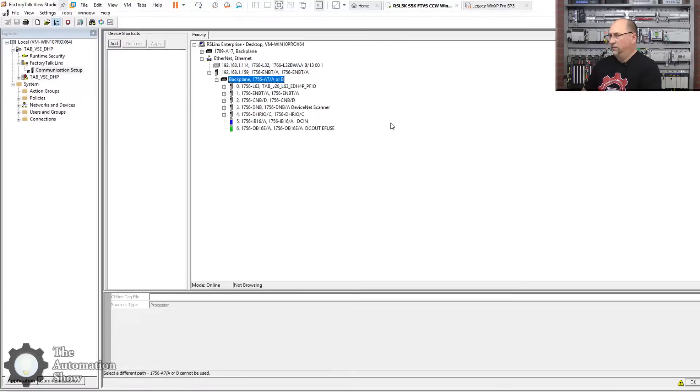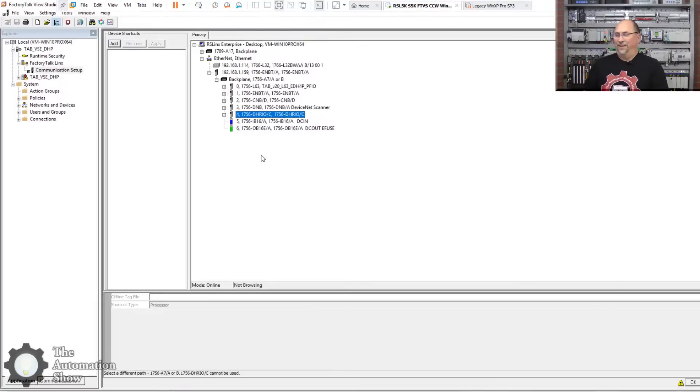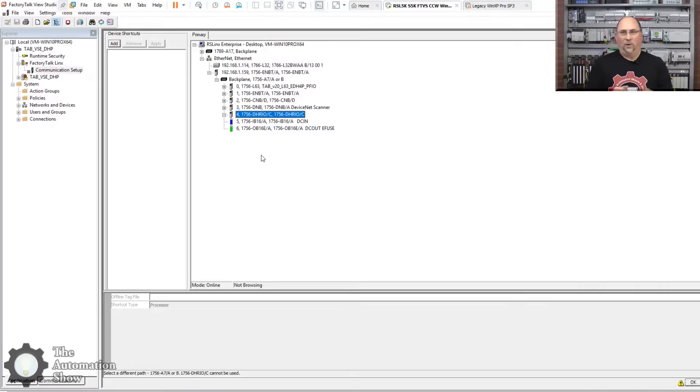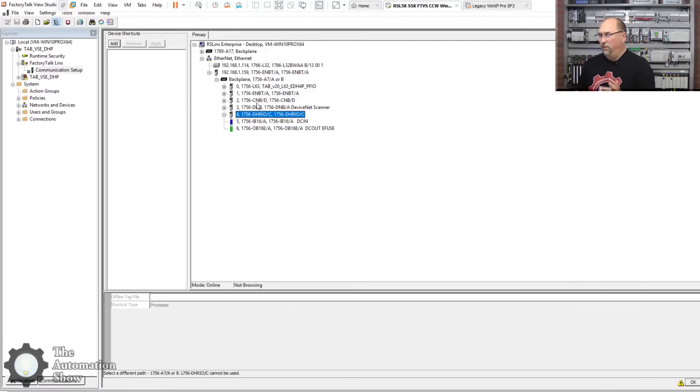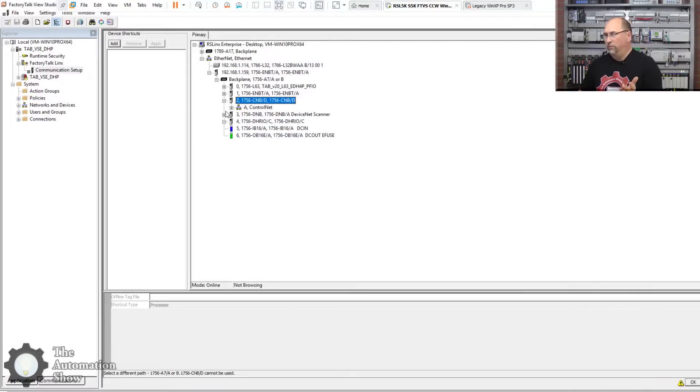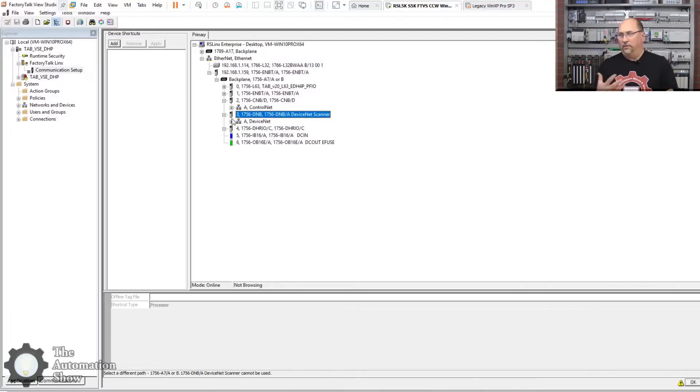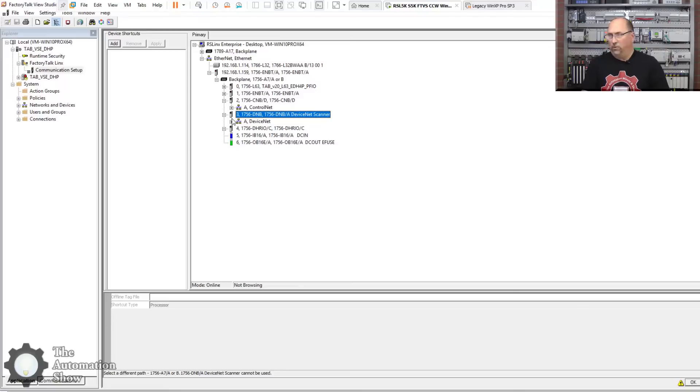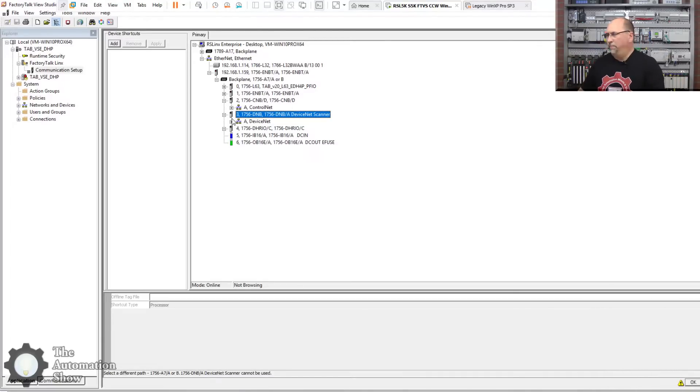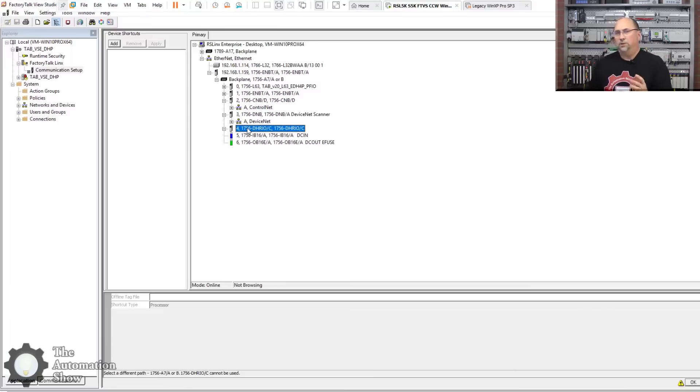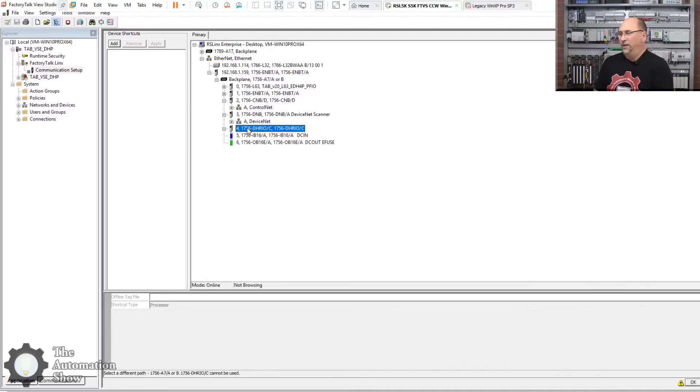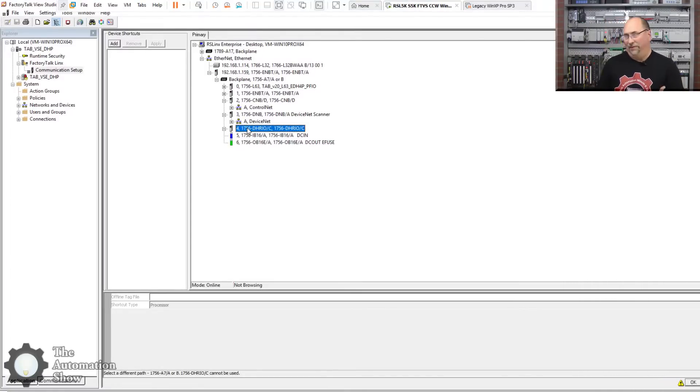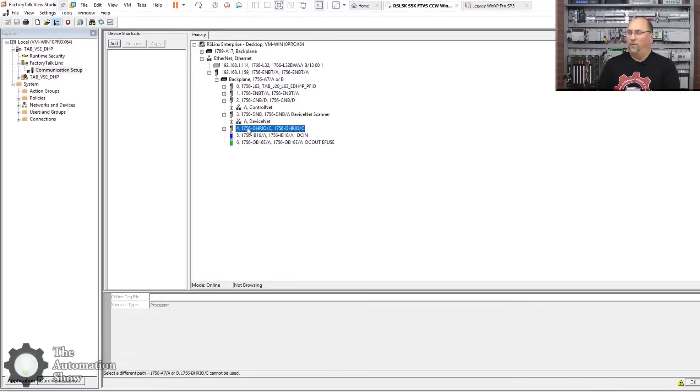And let's open that up, communication setup. Okay, we'll go out through the Ethernet, go through our ControlLogix rack here, and out the DHRIO, and we're not seeing anything. And the reason is RSLinx Enterprise or FactoryTalk Linx cannot browse through different network types. In other words, it has no problem going through ControlNet or going through DeviceNet because ControlNet and DeviceNet are both CIP networks—they use a CIP protocol for that seamless routing and bridging. But DH Plus is not CIP. It's more like PCCC.